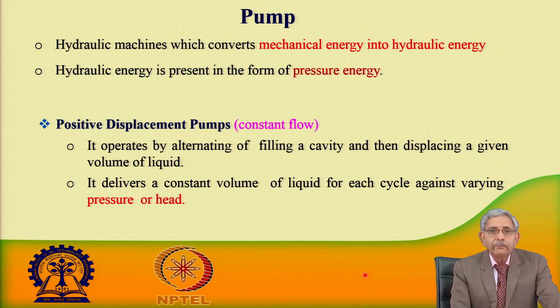It operates by alternately filling a cavity and then displacing a given volume of liquid. It delivers a constant volume of liquid for each cycle against varying pressure or head. The non-positive displacement pump is just the reverse, it has an inverse relationship between discharge and pressure head, meaning at low head the discharge increases, hence the power requirement remains high.